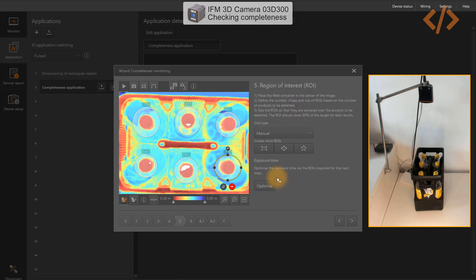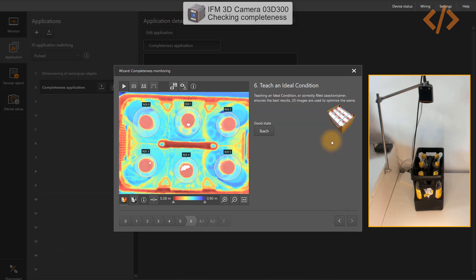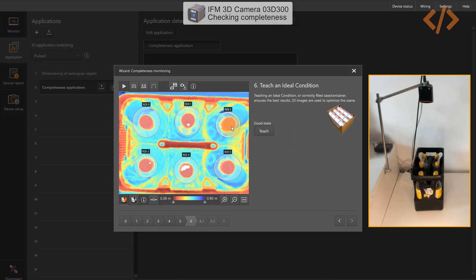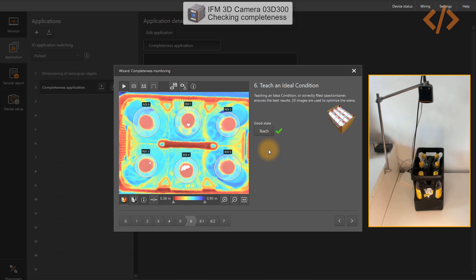Now you have to measure the good state — put all the bottles inside the container as you can see in my camera, and click Teach. The camera will find out how many pixels are in the area of interest, what the distance is between those pixels and the camera. Click Teach, let it do its calculations, and once you see the tick mark, click Next.